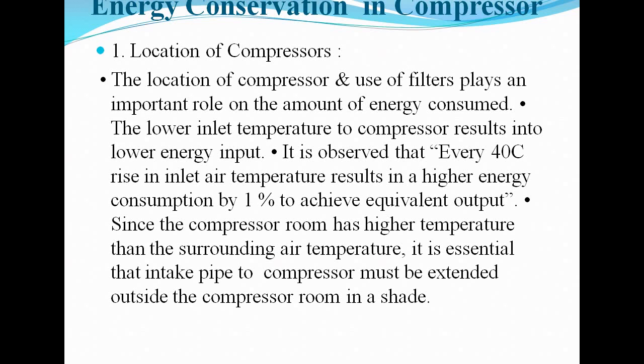Since the compressor room has a higher temperature than the surrounding air temperature, it is essential that the intake pipe to the compressor must be extended outside the compressor room in a shade. Now the compressor is located in a room, and as we start the compressor and use it for a certain period of time, the temperature of the room increases.